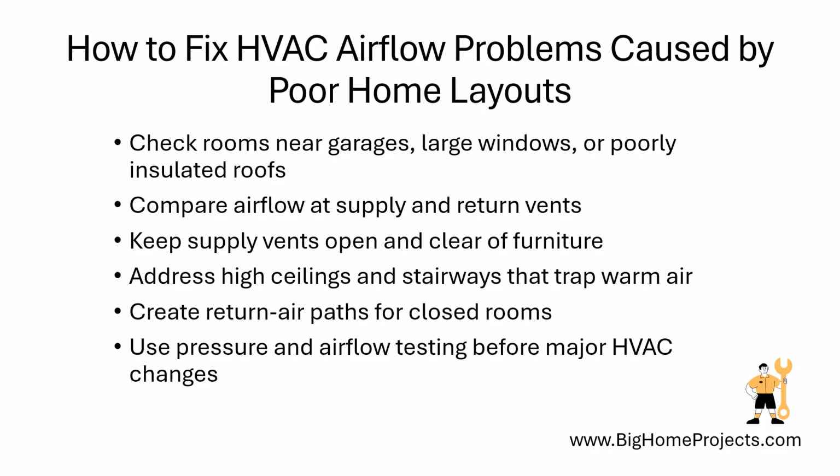One lesser-known issue is pressure imbalance. If a closed room has a supply vent but no return path, air pressure can build up and reduce airflow, sometimes pulling dusty or damp air through cracks. You can improve this by keeping doors slightly open, adding a transfer grill, or asking a qualified contractor to test the system with a pressure and airflow measurement.